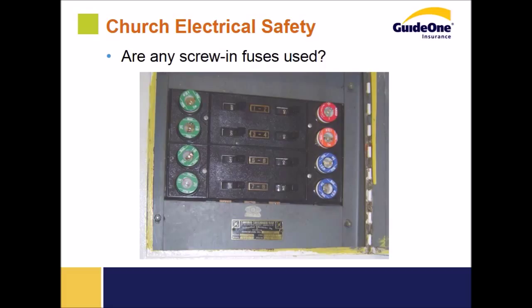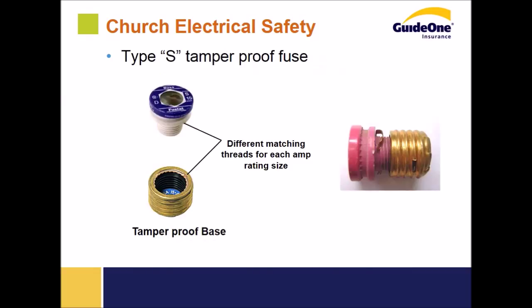Here's an obvious example of an older installation. The screw-in Edison-based fuses are still fairly common in our church population, and it's a concern for us. This type of thing needs to be noted. We do need to make the recommendation for a preventive maintenance program, and in some cases we will recommend that they update their system. We're still working with churches, and in some cases, when the funds aren't available and the electrician can tell us that the system is adequate and provides the proper protection against overcurrent and fire, we will certainly allow them to keep their old system in place.